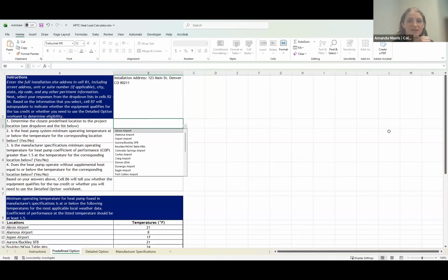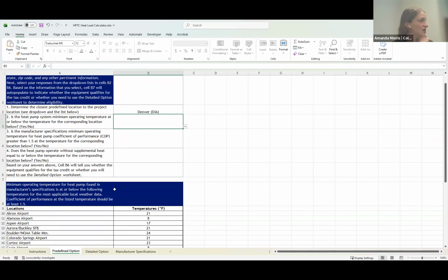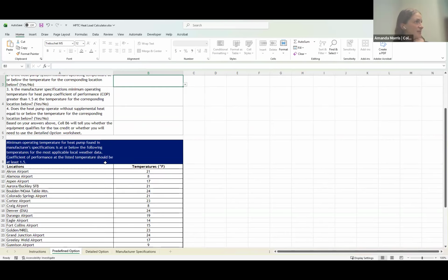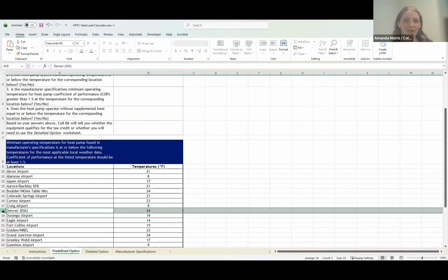For Denver, I see in the list below that the closest airport is DIA. I go down to the section for minimum operating temperature. I see in the list that the minimum operating temperature for Denver for a favorable COP above 1.5 is 24 degrees. I look at my cut sheet and see 15 degrees and a COP of 2.0.